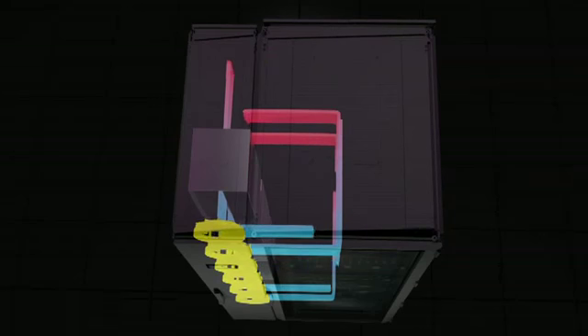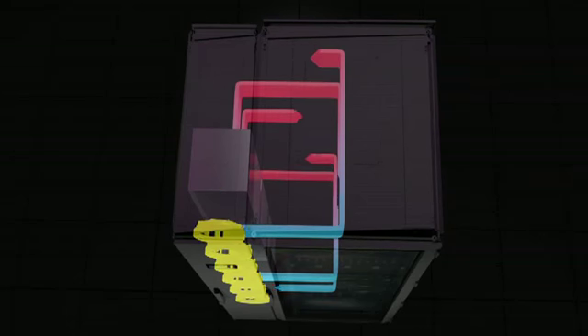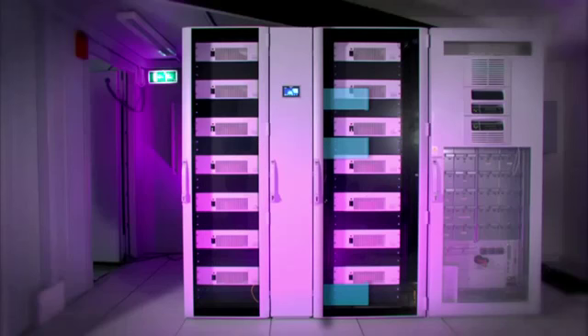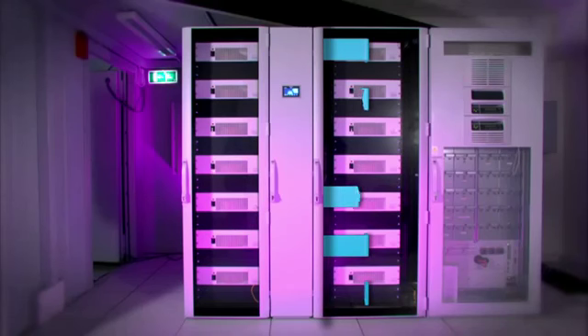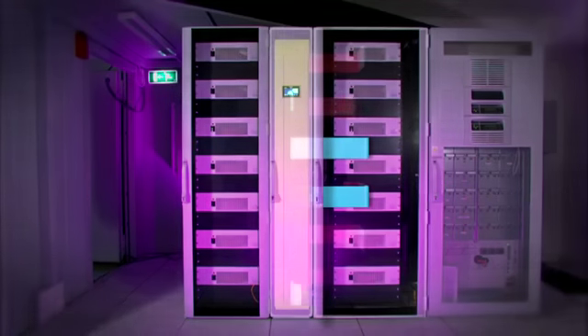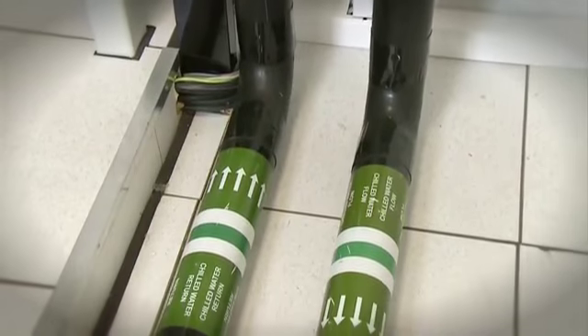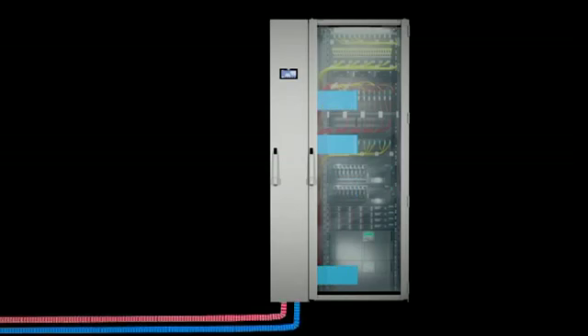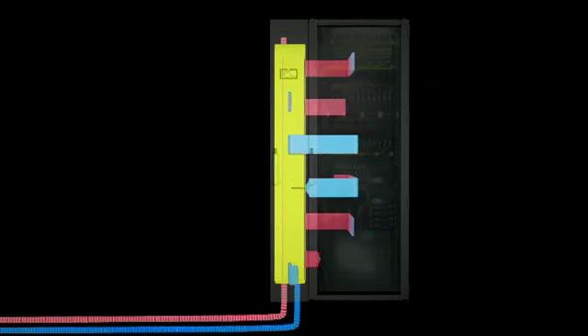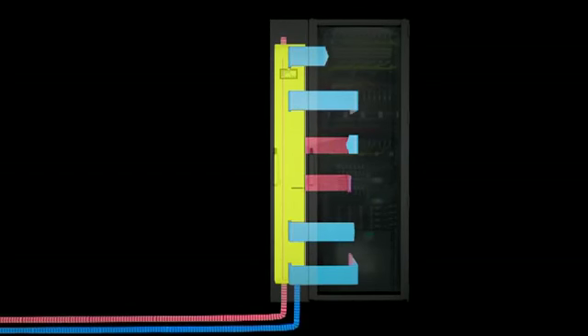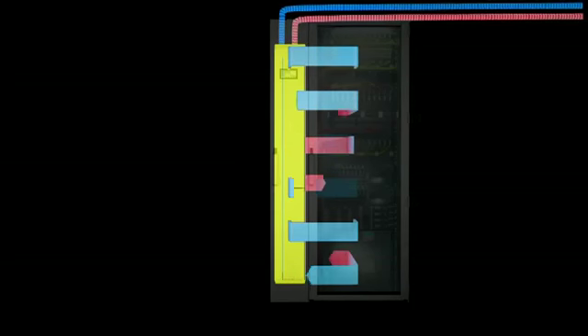This is a closed-loop cooling system which focuses the cooling directly where it's required. Physically separating the hot and the cold air paths so they can never mix also significantly increases system efficiency. Water is generally readily available in most data centers, so installation of the LCP Plus can be as simple as connecting to your existing chiller circuits. The LCP Plus can be fed with water from below if you have a false floor, or from above. With a greater efficiency than traditional open-loop systems, again the LCP Plus can give long-term financial gains.